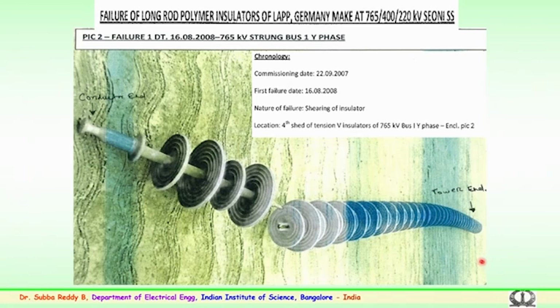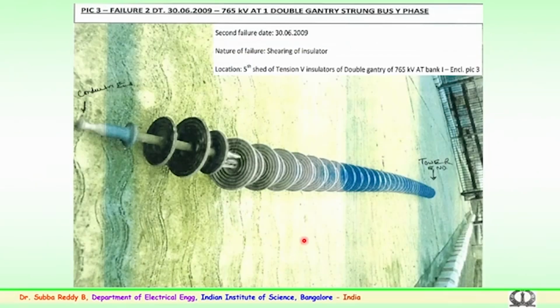These are some of the failures which have been reported because of brittle fracture. You can see after the fourth shed, over a period of time, the brittle fracture has happened and detachment of the insulator has been observed in the field. So, very important. With polymer insulators at present, a lot of things have been happening, and with these studies of failures, people have improved their performance, newer technologies are being used, and new methods, particularly on the manufacturing side, are being adopted to see that such failures would not happen, and that long-duration performance must be reliable. That is one of the important aspects of this type of insulator.